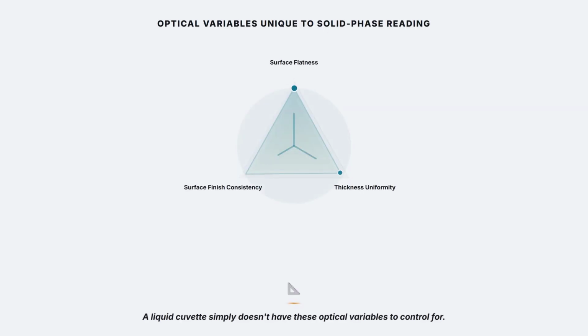Slide surface geometry itself introduces optical variables that a liquid cuvette simply doesn't have. Surface texture, slight thickness variation, and even minor curling or warping of the slide can scatter light unpredictably. Manufacturing tolerances on slide flatness and surface finish are tightly controlled specifically to keep this scatter-related noise below the instrument's detection threshold. Keeping the optical reading path itself trustworthy, practically.